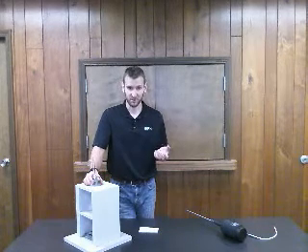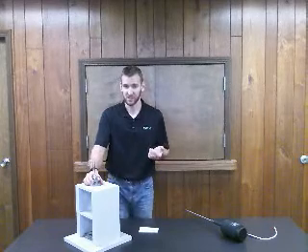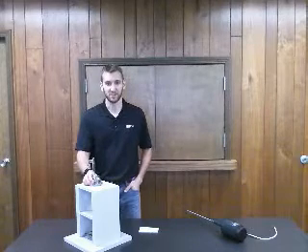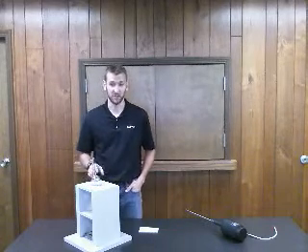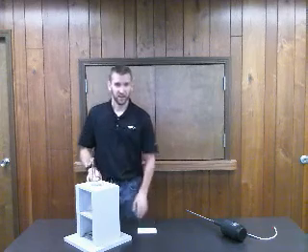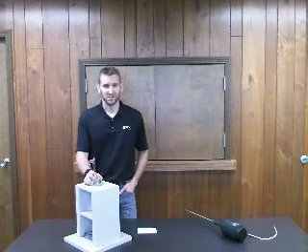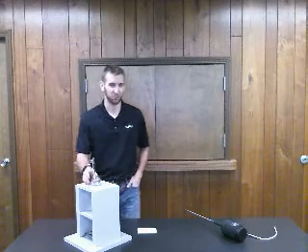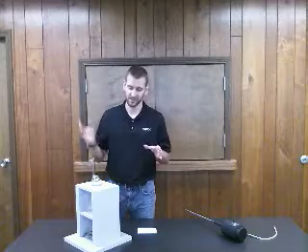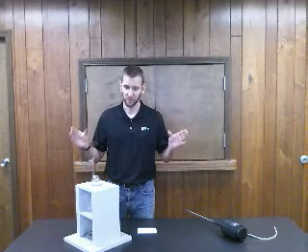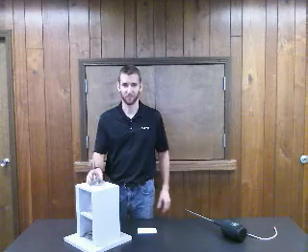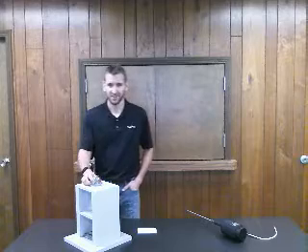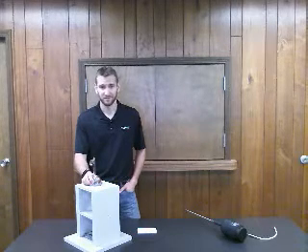Once properly frozen, the ice layer will last about 8 hours, depending on how well the insulation is for the containment unit. In some extreme conditions, it will last nearly 6 weeks, but this is using a maintenance bath that recirculates cool water and is constantly cooled, with a very thick amount of insulation on either side. With a properly prepared triple point cell, the temperature probes can now be calibrated.